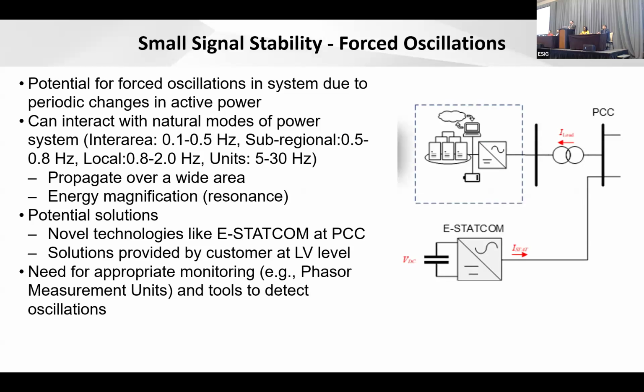Continuing with stability, now forced oscillations. This becomes an issue again with the AI type data centers I talked about. Remember I talked about how the load can be fluctuating, and it's especially problematic if that load variation is cyclic. Seems like that can be the case here, that it's cyclic, meaning it repeats, say, every few seconds, and it's 24/7 operation.